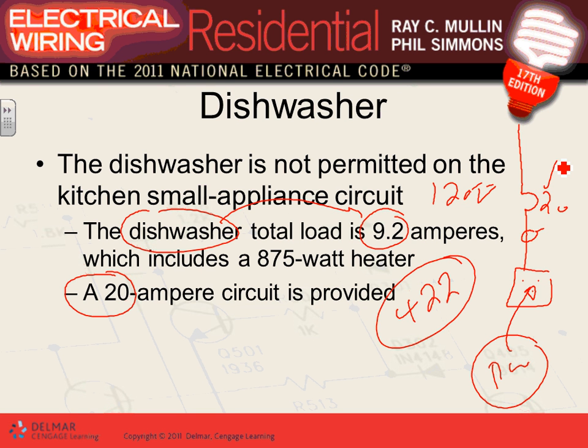a circuit breaker to protect it from short circuit and ground fault, a cable to send the power to it, a plug to plug it in if it's not hardwired. If it's hardwired, then you need a disconnect. Any comments, any questions?